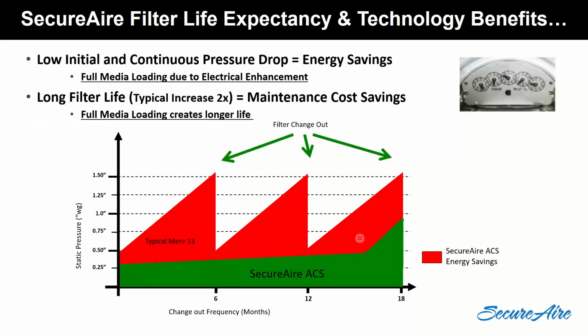By the way, originally when we were doing some of these, we were doing it for energy-saving projects, right? A hospital that needed good filtration wanted that Merv 14 or 15 filtration. They could do this because it's only a 0.28 inch pressure drop. They could do it at a relatively low fan energy, which was a cost savings mechanism. That was literally what contractors and engineers were explaining to the hospital guys. They were selling it to them based on energy saving projects. And since then, we're obviously doing it for other reasons now because it does a good job of catching germs. But it was really an energy saving project is how this kind of started for us 10 years ago.